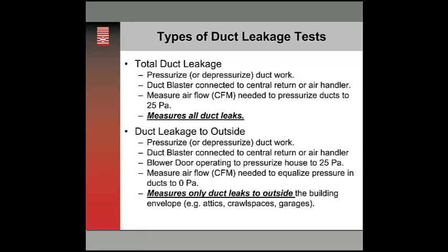So there are two different types of duct leakage tests. You can talk about the total duct leakage test, where you pressurize or depressurize. And depressurizing is probably going to get you your tightest result. Not that pressurization doesn't work, but when you depressurize, you're kind of sucking that duct mask film onto the ductwork to help seal it up a little bit better. But it's a little trickier setup. It's a little bit extra setup on your Minneapolis Duct Blaster. But both will work, so you can pressurize or depressurize.